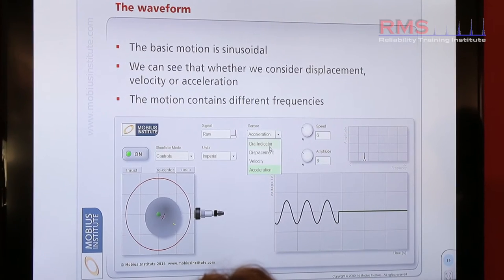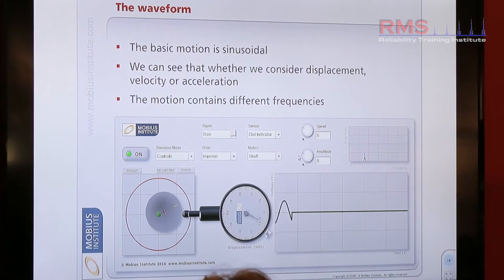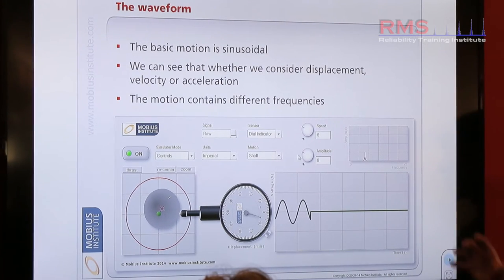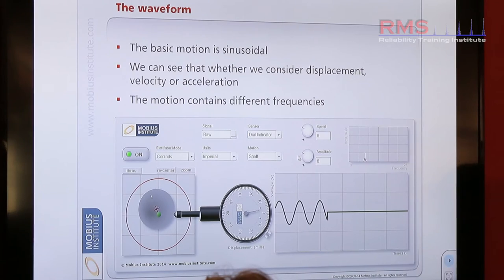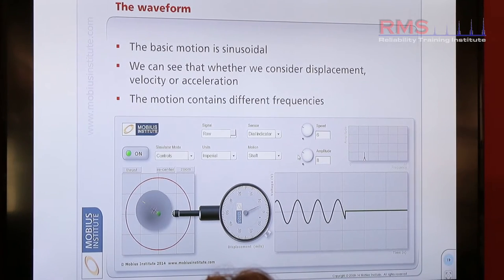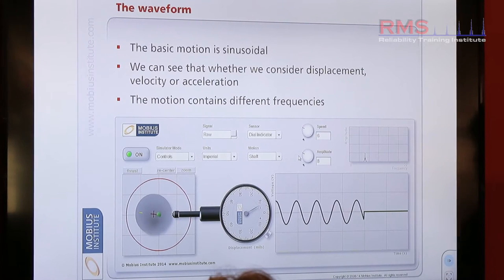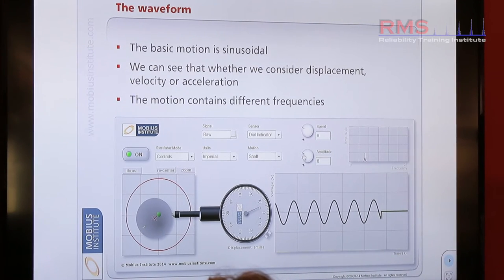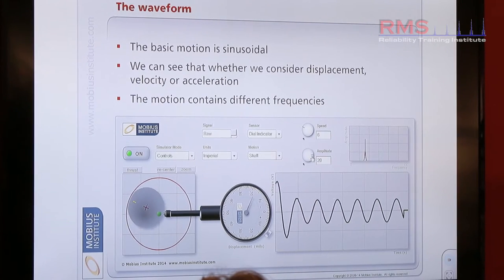So obviously if my shaft had a fan on it and there's a heavy spot, it's going to cause it to vibrate at a frequency of once per rotation due to the heavy spot. If the heavy spot gets greater because product's building up on a fan blade maybe, then obviously what will happen is the amplitude — the level of the vibration — will grow.